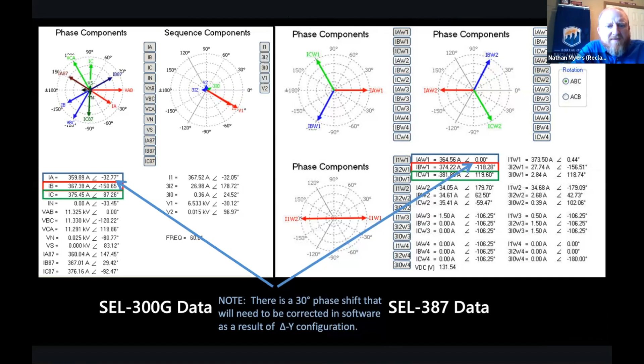And if they are, then we say that the instrument transformers are working correctly, we're receiving the signals correctly at the relay itself, and that everything appears to be fine. If we were to get values that were outside of tolerance, then that's when we'd want to have an alarm. One thing that you will notice here is the phase angles on the 300G are different than the phase angles on the 387, and that has to do with the delta-Y configuration within the transformer. So we'll have to be able to account for that as well within the end solution. Next.